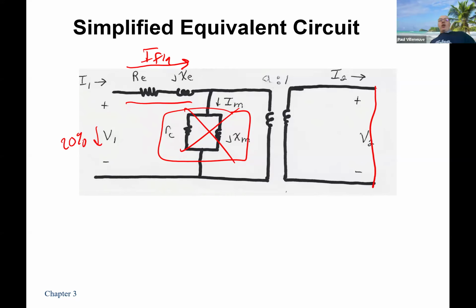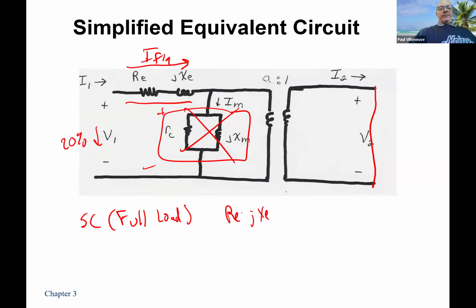So I'm going to get big voltage drops across my RE and JXE and very little losses across here because I'm essentially going to have almost no voltage. And when you look over here and I reflect it through, you can even see that's pretty low. So the short circuit test, or sometimes the full load test, is going to give me RE and JXE.